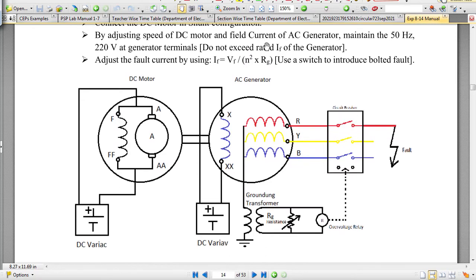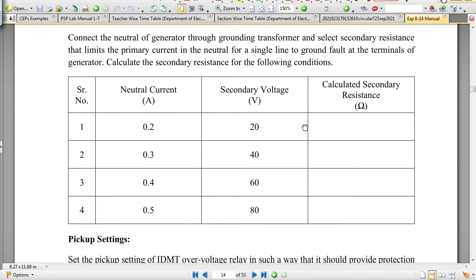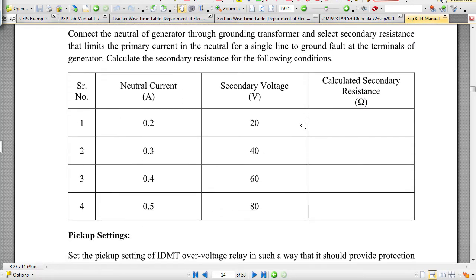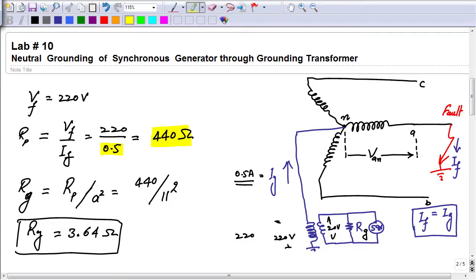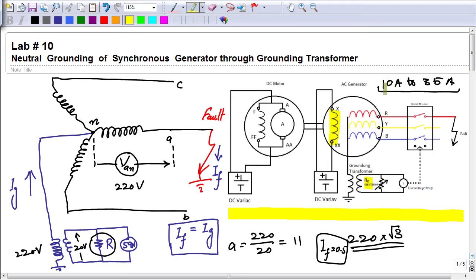Once the student calculates the value of resistance to be inserted on the secondary side of this grounding transformer, next we will see how to detect the fault. Look at this fault current. This fault current is very small. Even in power systems we have seen that the grounding impedance is designed in such a way that it will limit the fault current from 10 ampere to just 35 ampere. That is not a very high current, so it is not easily detectable with the help of an overcurrent relay connected here in the phase circuit. So to detect a ground fault, we will use this mechanism.